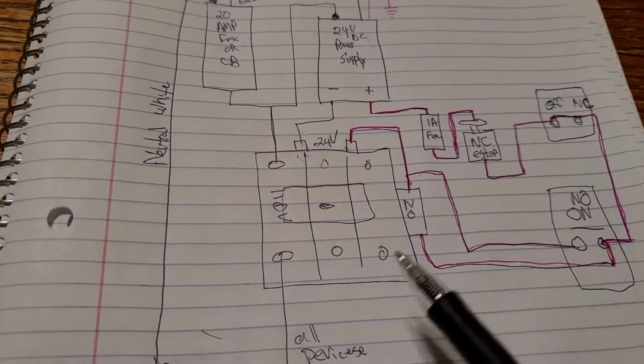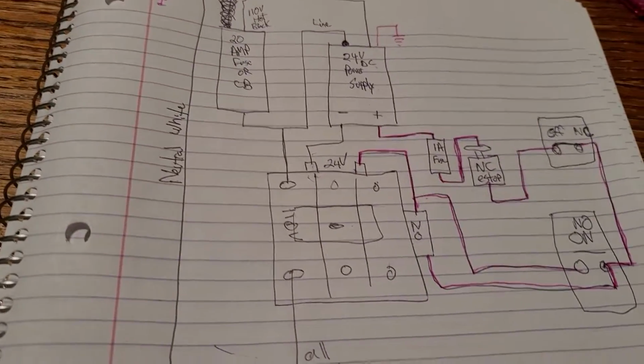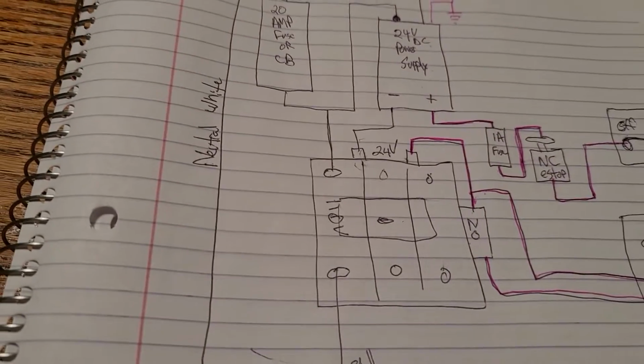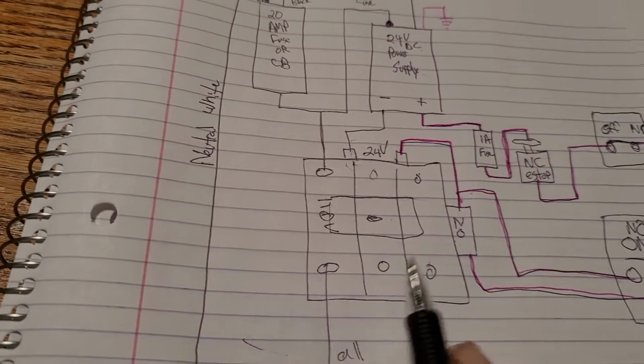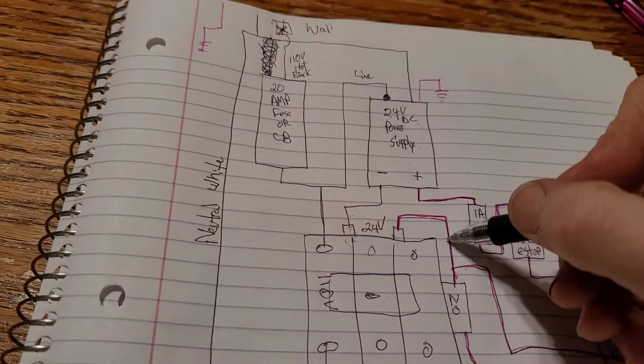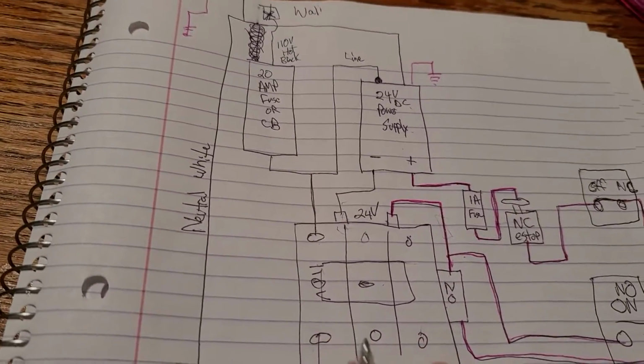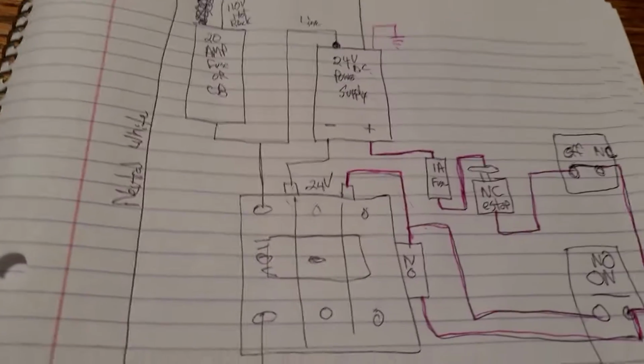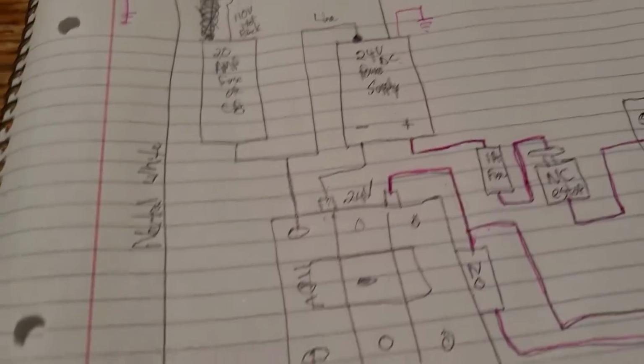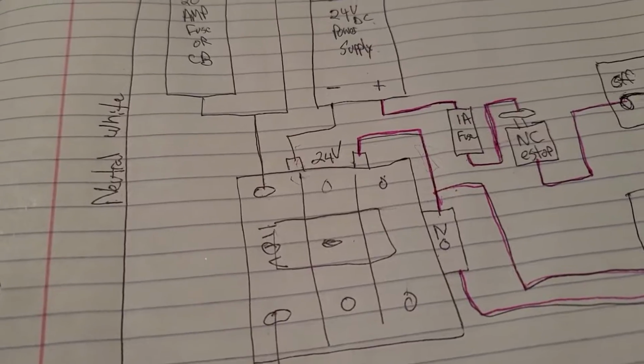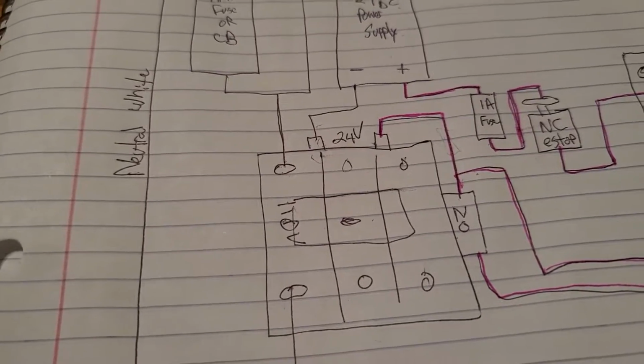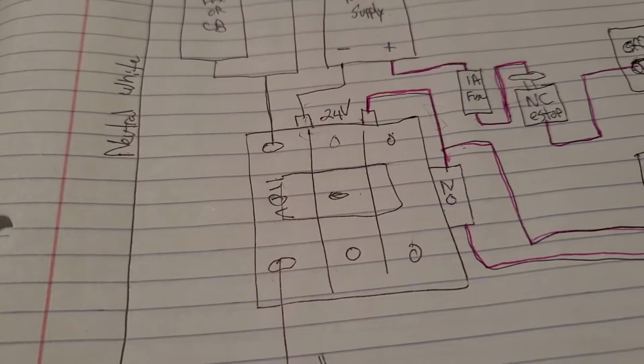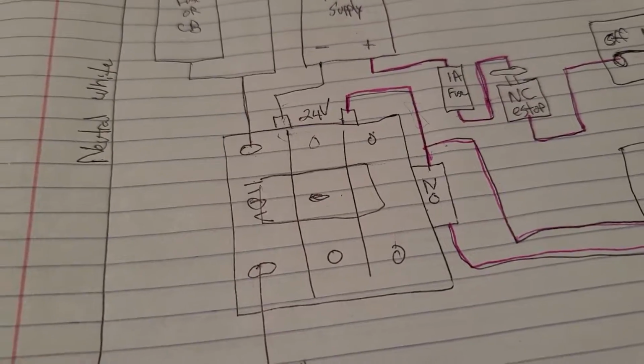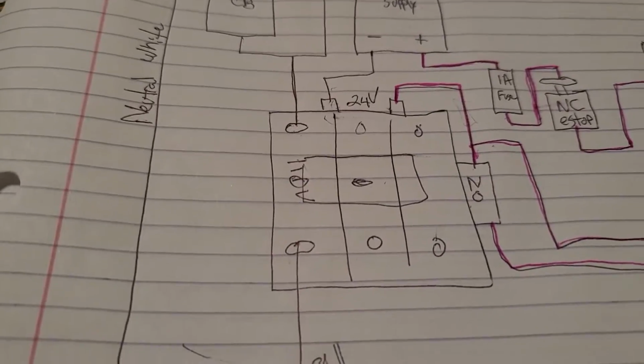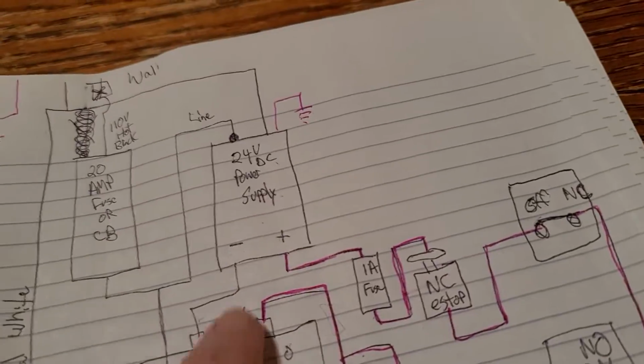Now, sidebar, if you're going to install an overload relay, which is also potentially a purchase with the contactor, this connection would go right here, right? But they get bolted to the bottom, okay? And so the point of all that is, on that overload relay, when it's not at amperage, it stays closed. But if it goes above a certain amperage, it opens. Or temperature, I think, is the thermal relay. Don't worry about that right now. Let's just worry about the contactor.